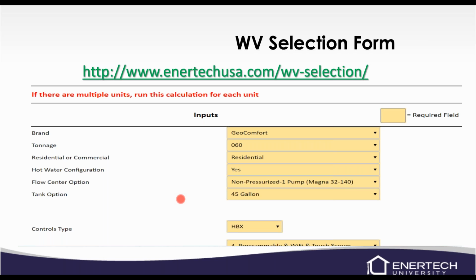But either a pressurized or a non-pressurized system, if you're somewhere where the water temperature is going to get to 30 degrees, you're going to have antifreeze in it. So maybe down in the Caribbean or down in Florida or Texas, you may not need antifreeze, but here in Illinois, anywhere in the Midwest, up north, Canada, you're definitely going to be below that 30-degree mark. And so anytime we get below that mark, there will be antifreeze in the system.